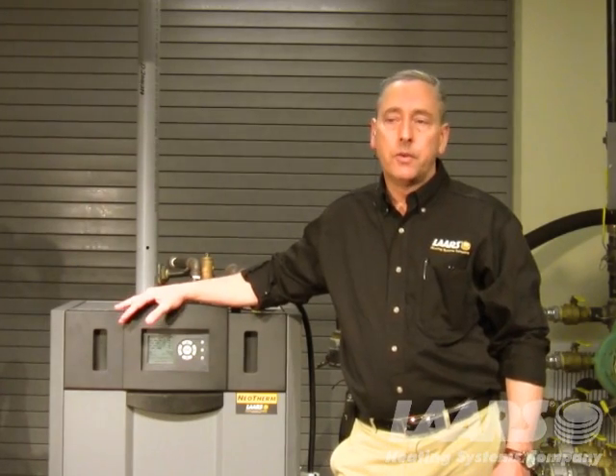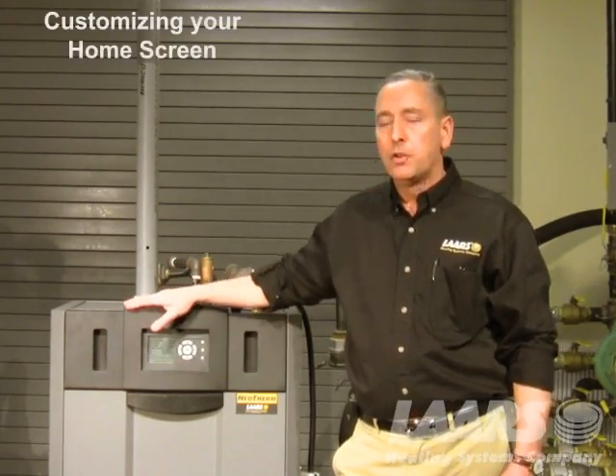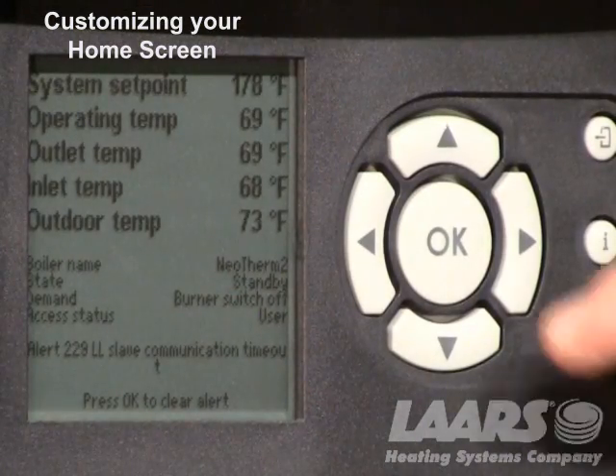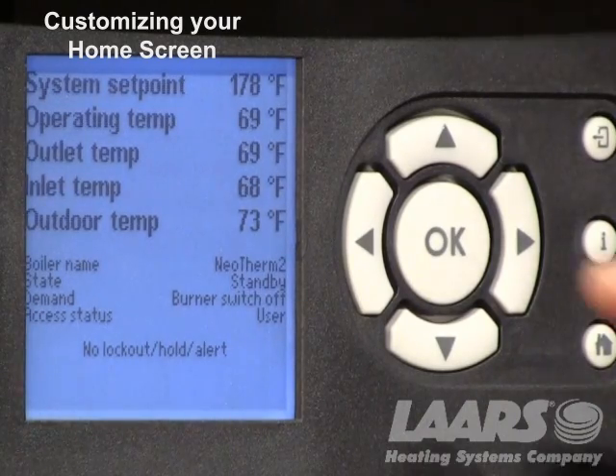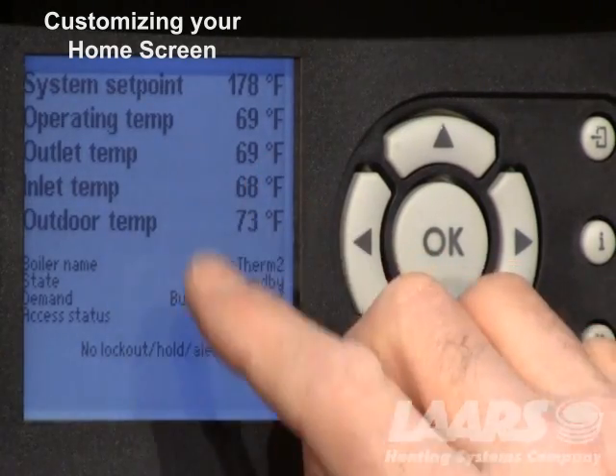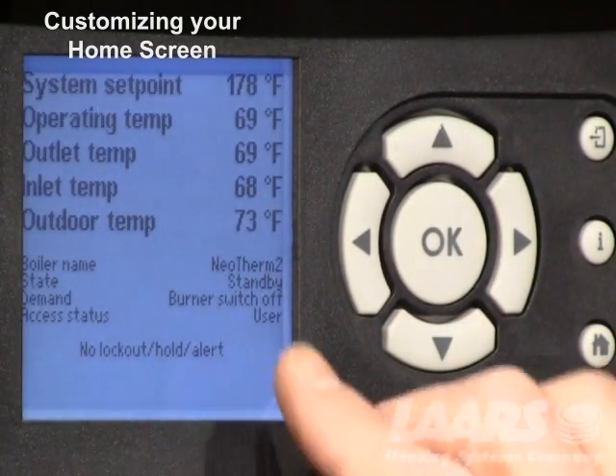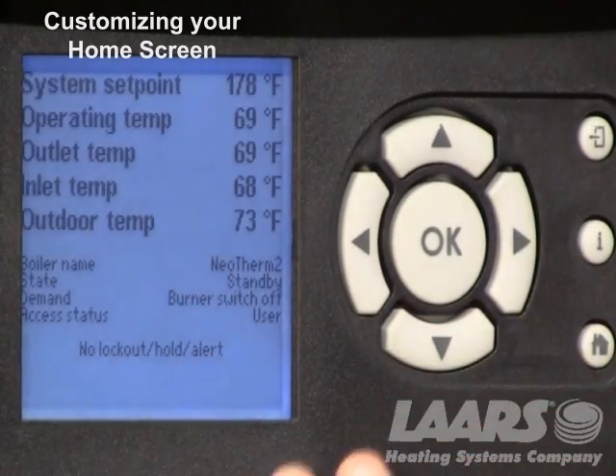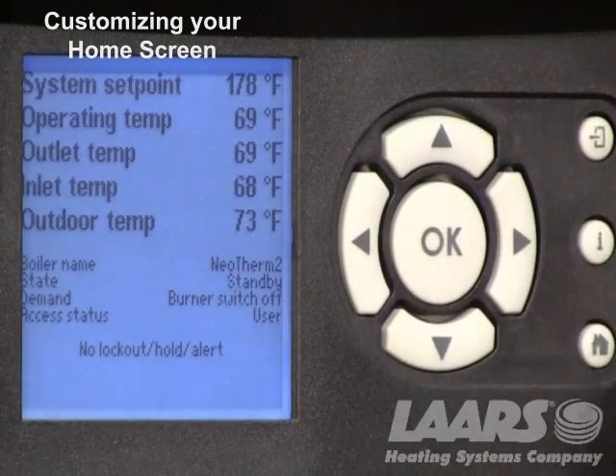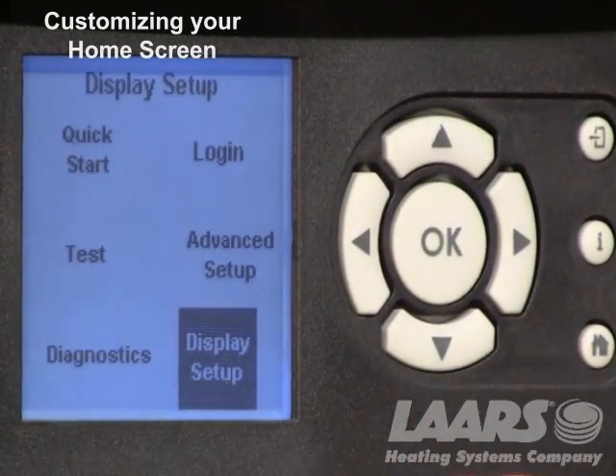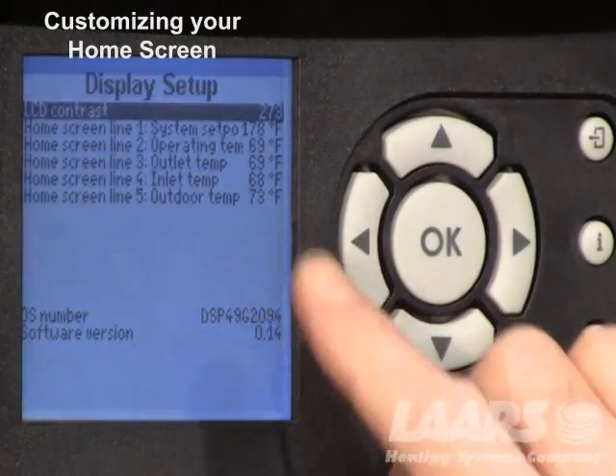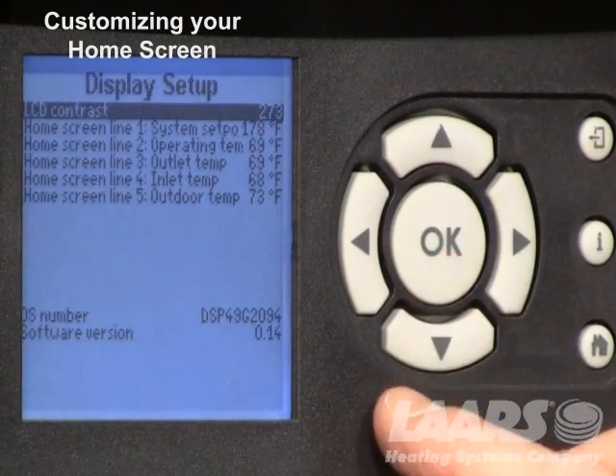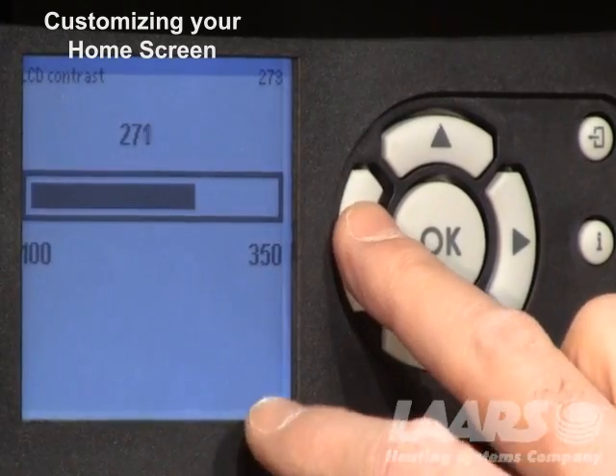Now that we've set up master and slave controls to cascade, you may want to change the prompts on the home screen for your lead lag set point and operating temperature. On the home screen you can change the top five line items. Defaulted from the factory are system set point, operating temp, outlet temp, inlet temp, and outdoor temperature. If you don't have an outdoor sensor hooked up, this will read open. Hit the i icon, scroll down, and choose display setup. Press okay — the first thing highlighted is the LCD contrast, which controls the screen brightness. Depending on the lighting in the mechanical room, highlight this, press okay, and use the left or right arrows to lighten or darken the screen.